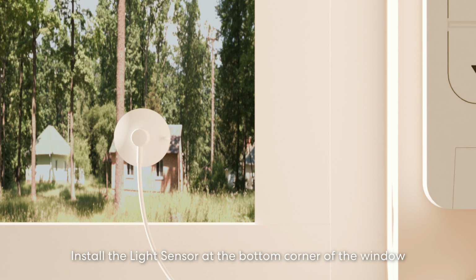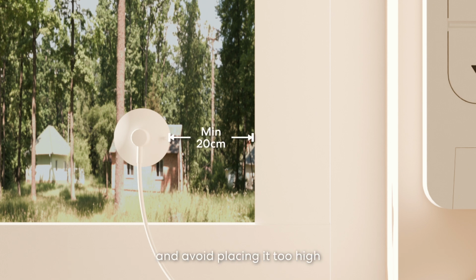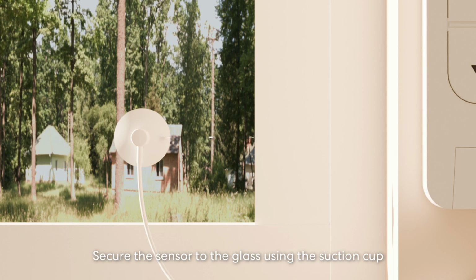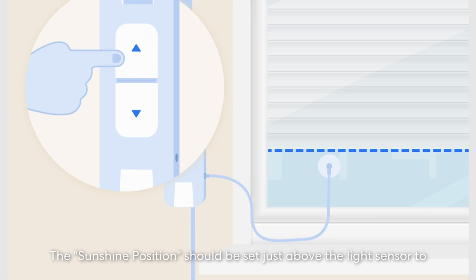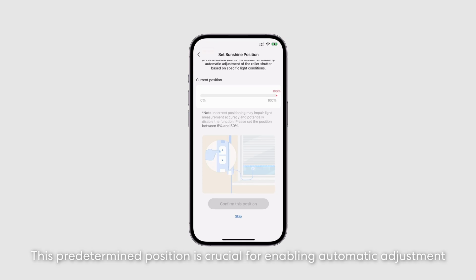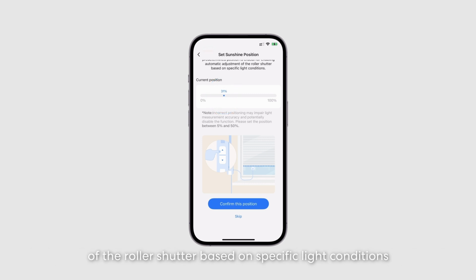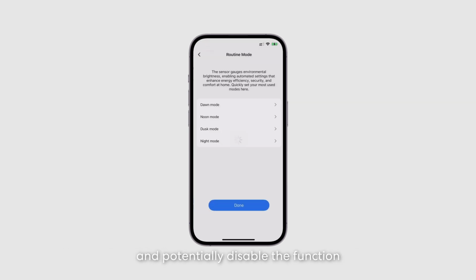Install the light sensor at the bottom corner of the window, following the diagram, and avoid placing it too high. Secure the sensor to the glass using the suction cup. The sunshine position should be set just above the light sensor to ensure the sensor is not obstructed by the roller shutter. This predetermined position is crucial for enabling automatic adjustment of the roller shutter based on specific light conditions. Incorrect positioning may impair light measurement accuracy and potentially disable the function.